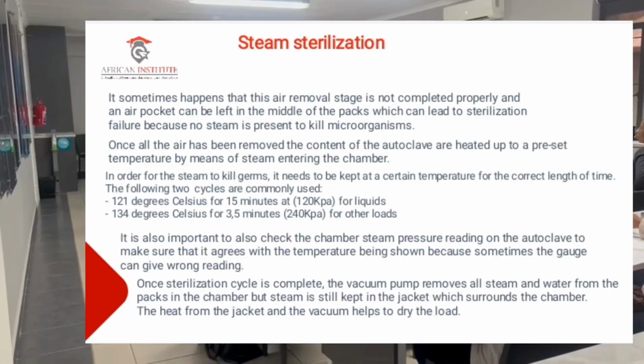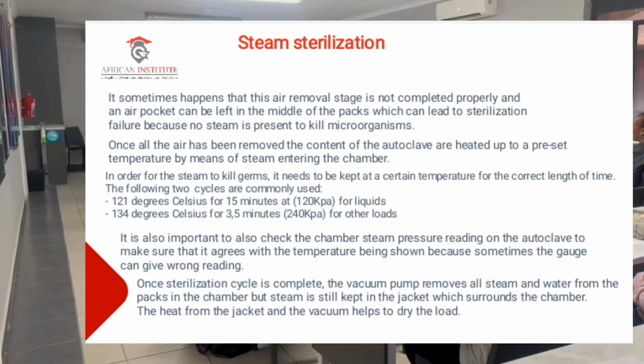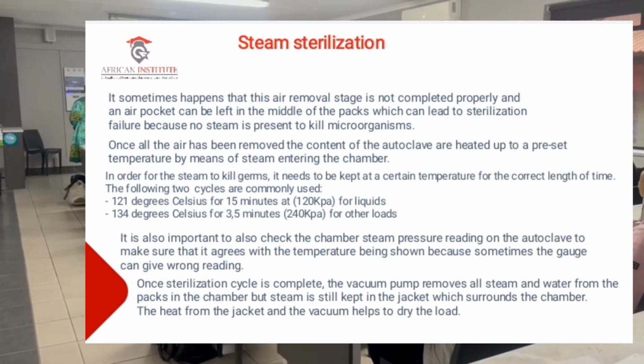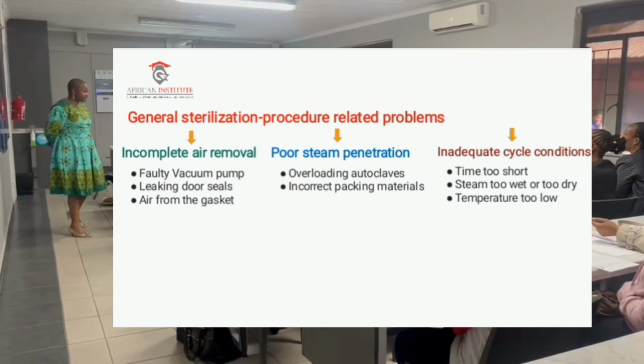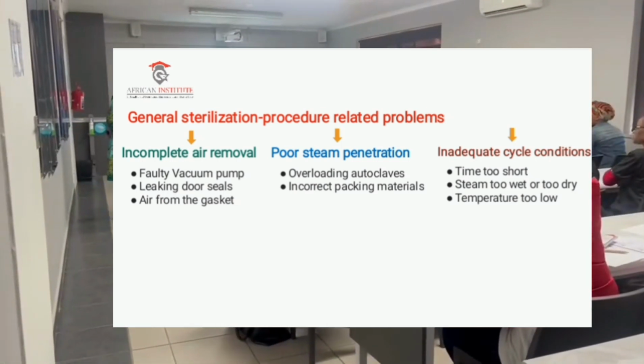It sometimes happens that this air removal stage is not completed properly, and an air pocket can be left in the middle of the pack, which can lead to sterilization failure because no steam is present to kill microorganisms. Once all the air has been removed, the contents of the autoclave are heated up to the preset temperature by means of steam entering the chamber.